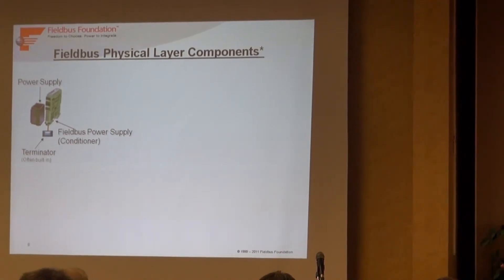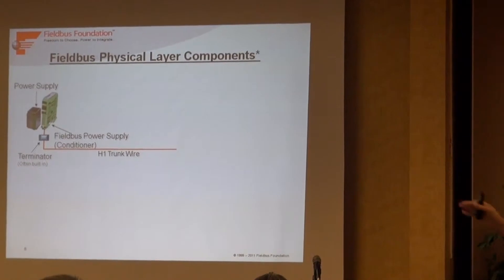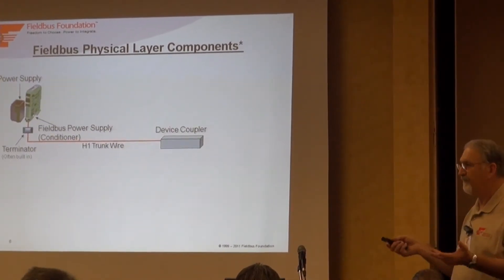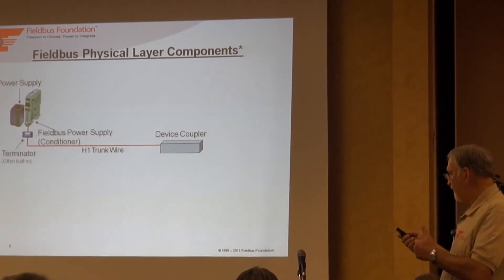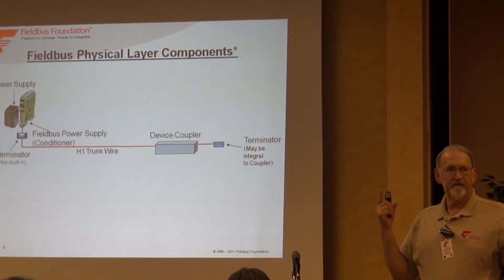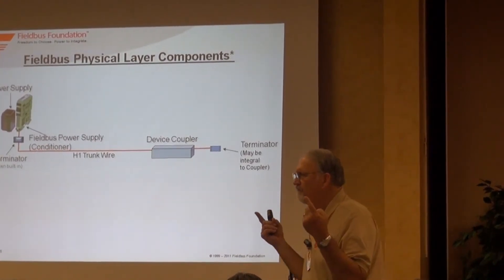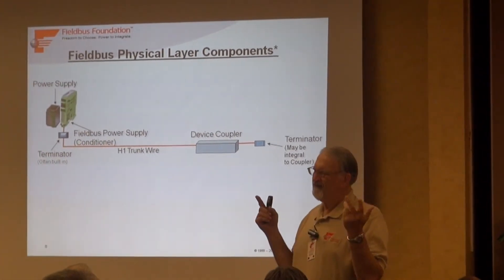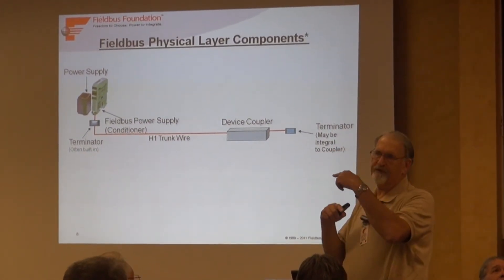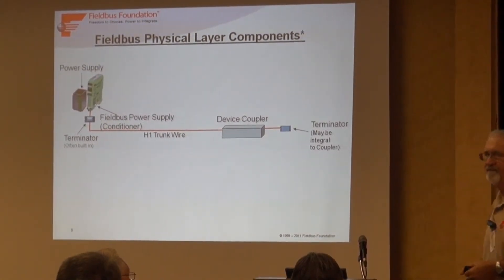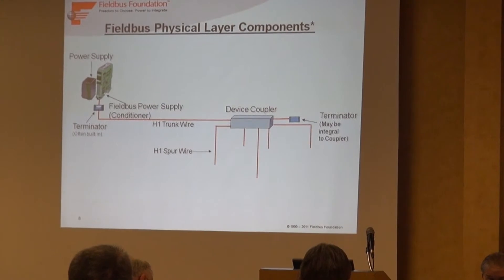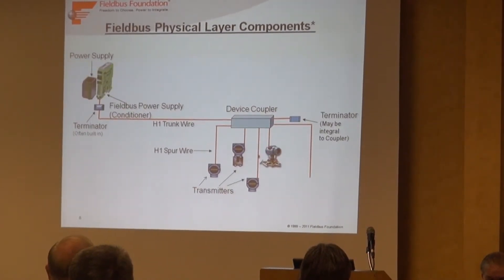You've got to have a terminator. You start out with a trunk, run it out to wherever you're going, to a device coupler. There could be several variations. In general, you're going to run out to a device coupler, and on there you'll have a terminator. How many terminators are there? Two. Can it be more? That's a trick question - yes it can be, but do you want it to be? No. It's not going to blow up if you have three, but it's going to affect your signal strength. Two is what you really want. Then you run spur wiring out to your devices - transmitters, valves, whatever.